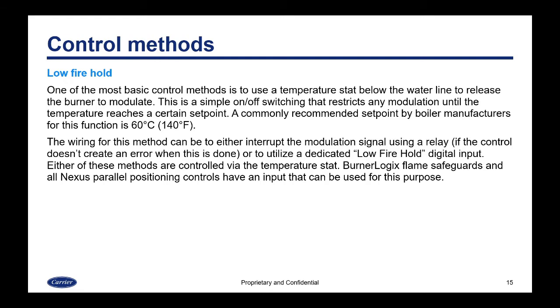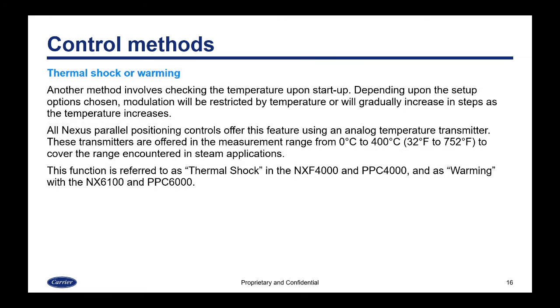One of the most basic control methods is to use a temperature stat below the waterline to release the burner to modulate. This is a simple on/off switching that restricts any modulation until the temperature reaches a certain set point. A commonly recommended set point by boiler manufacturers for this function would be 60°C or 140°F. The wiring can either interrupt the modulation signal using a relay or utilize a dedicated low fire hold digital input. BurnerLogix flame safeguards and all Nexus parallel positioning controls have an input for this purpose.